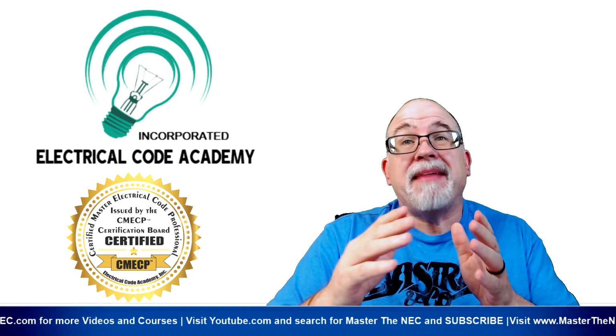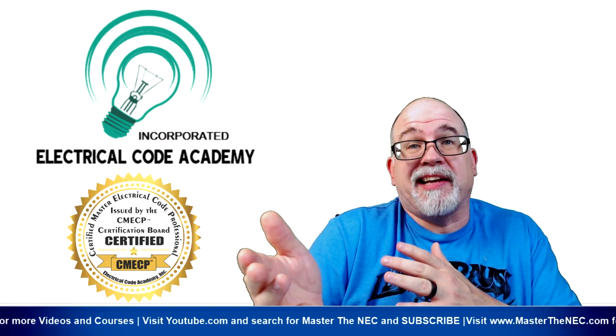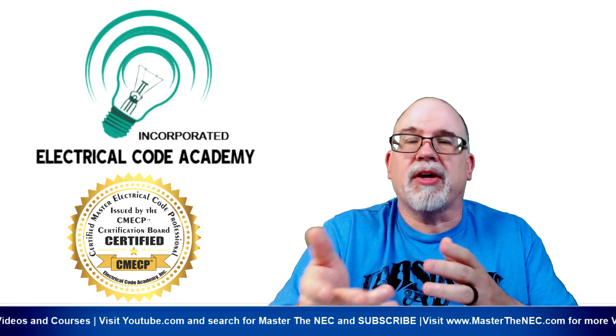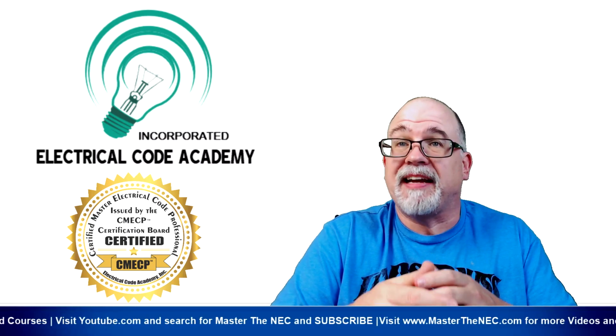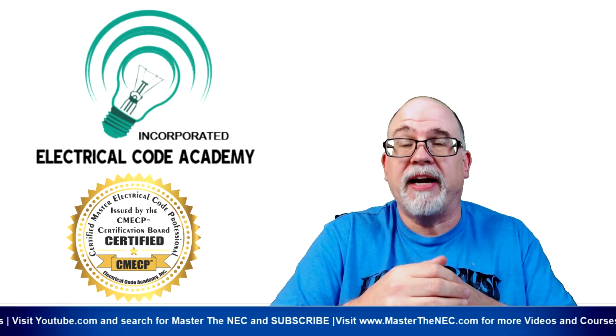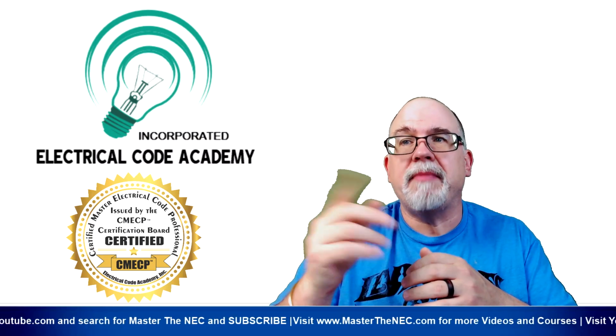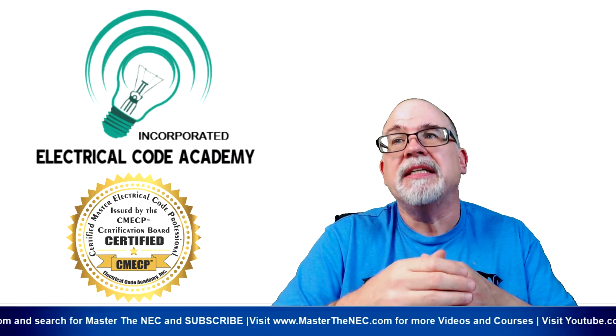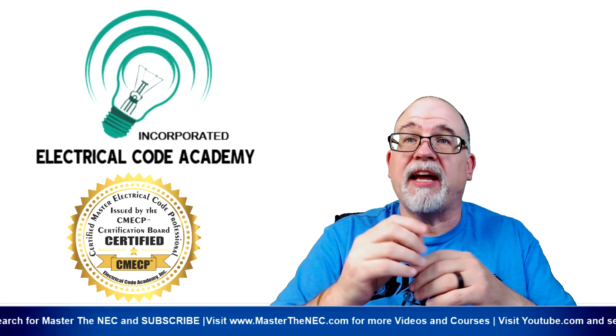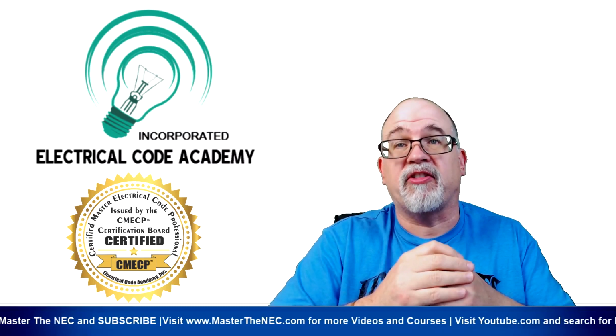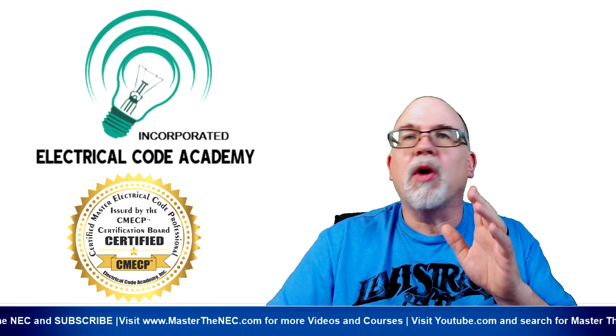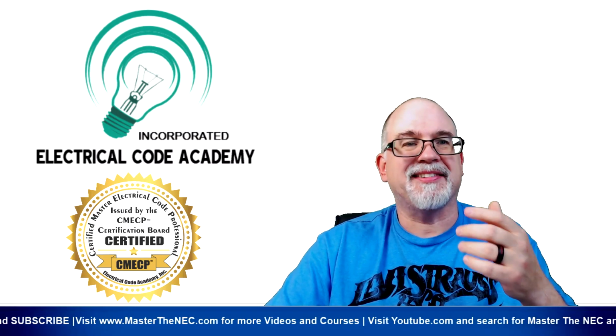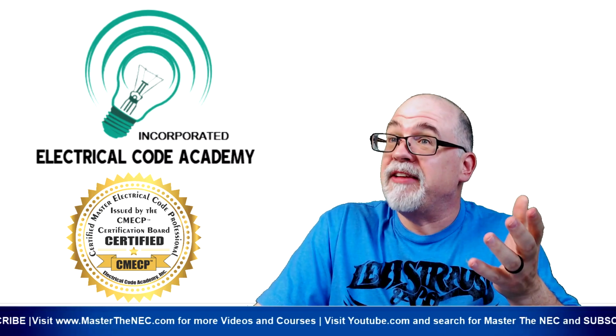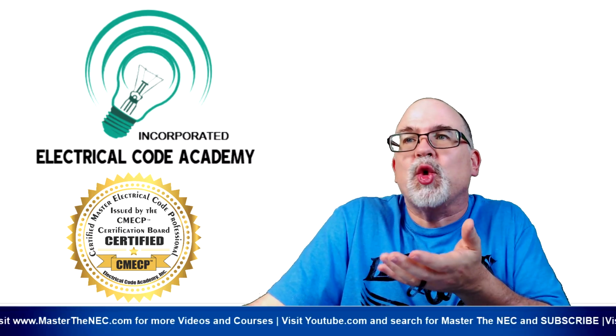Now, it doesn't mean that you can't have overcurrent protection on the secondary. It's just saying that those conductors can be considered protected by the primary under this rule, as long as you meet that secondary to primary ratio and all the multiplication that's qualifying it here in this C1. Okay, that's most we're going to talk about that one. Okay, so if that's the one you run into, just simply follow the rules that are written right here.